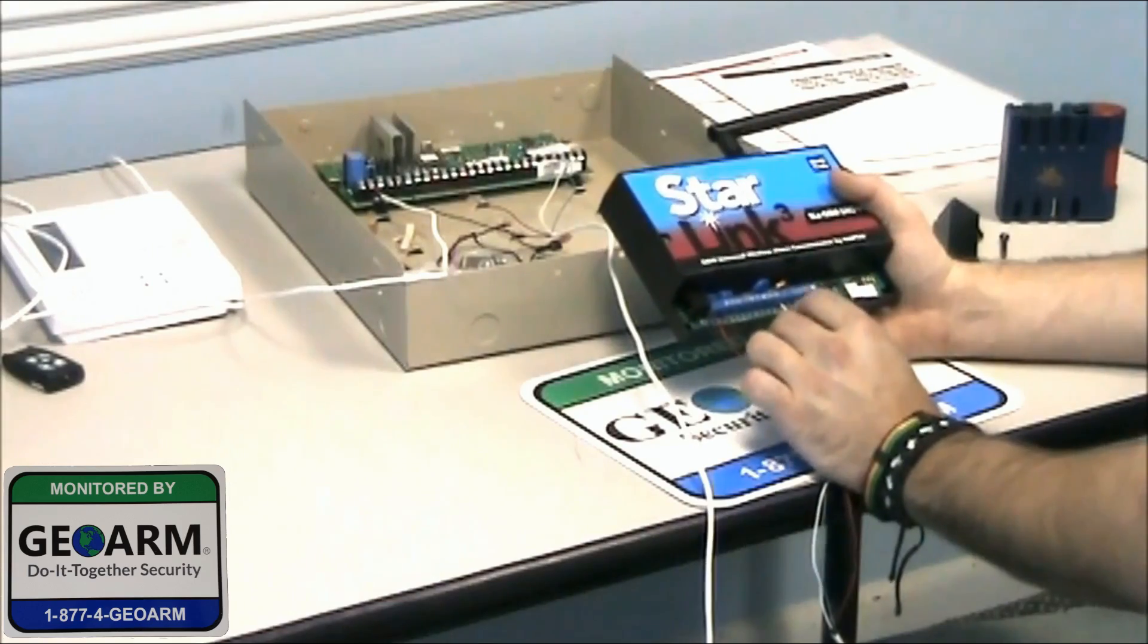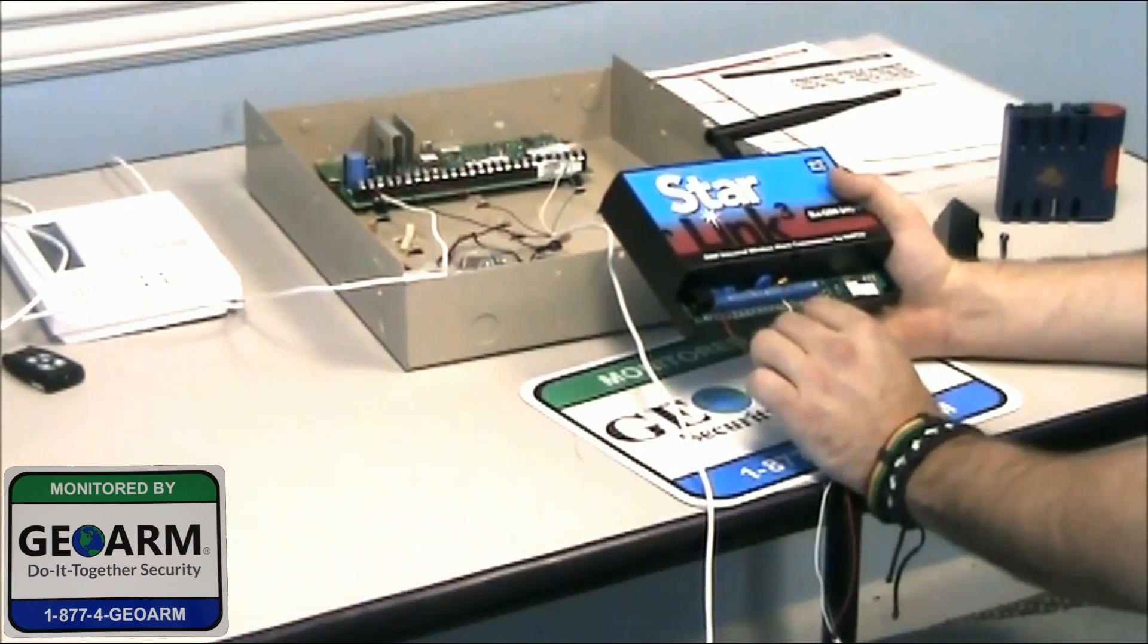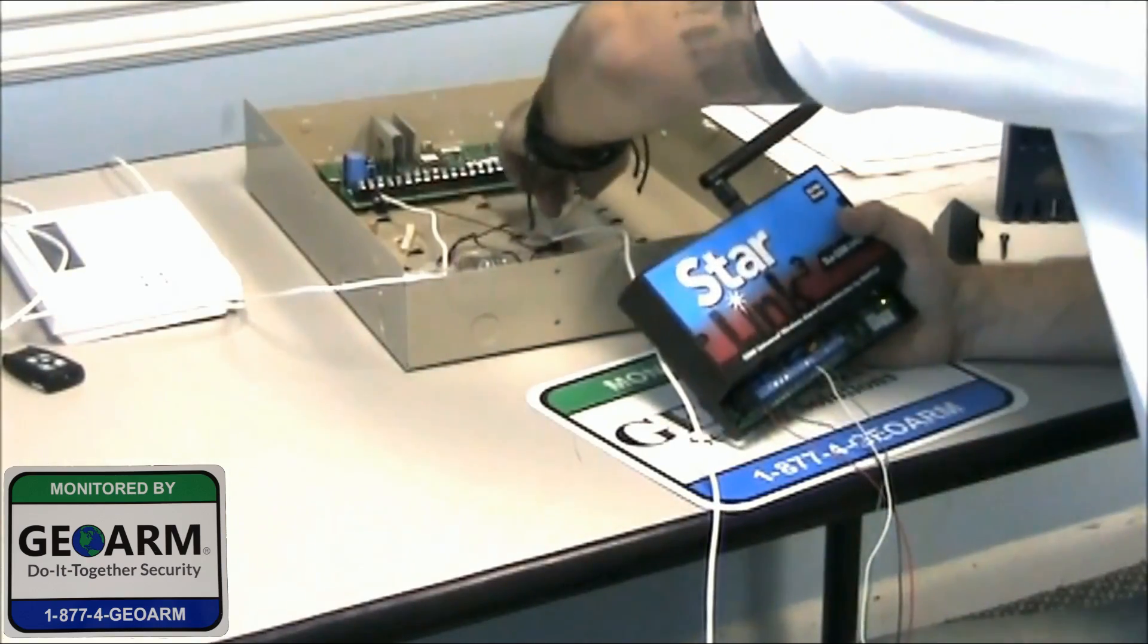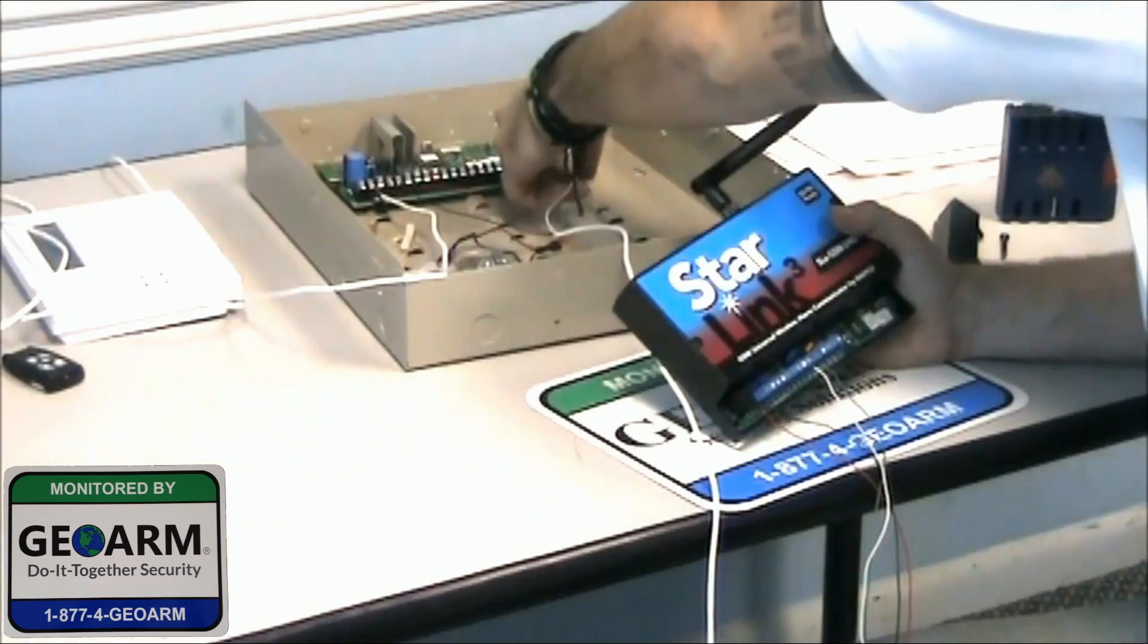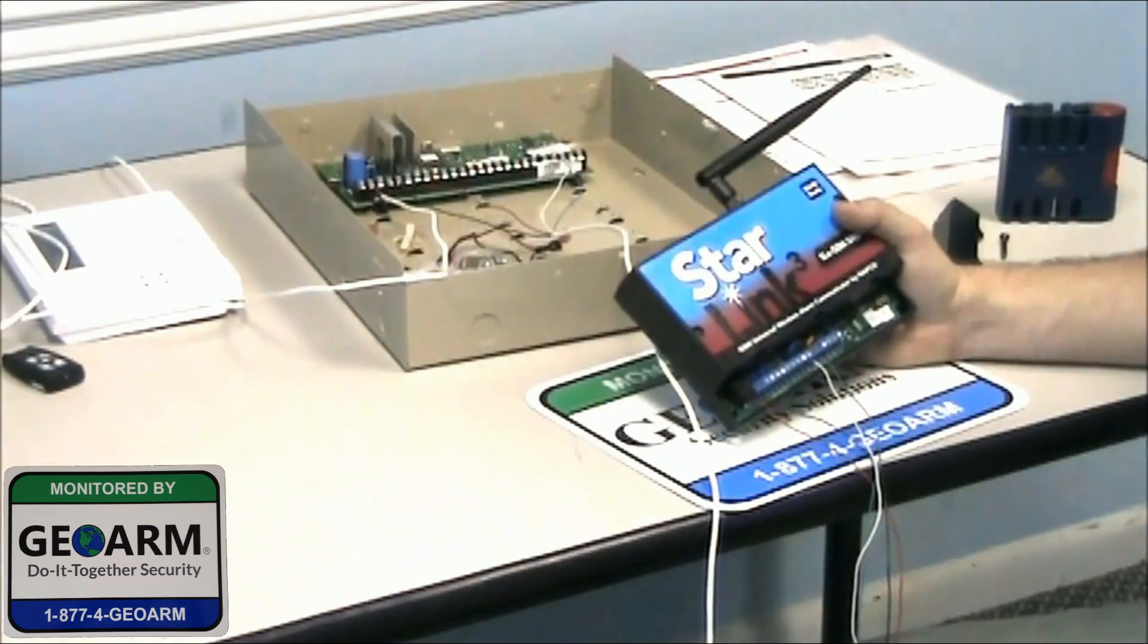panel ring, we're using a white wire and panel tip, we're using a green wire. Panel ring is going to run into terminal number 24 on the panel. And panel tip is going to run into terminal number 23 on the panel. And that's how you're going to wire it.